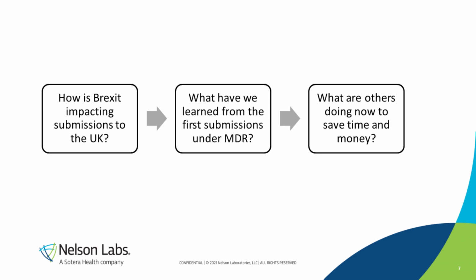And if you are submitting under the MDR and you have missed one of these steps, even if you've done the tests, even if the tests were done 20 years ago and it's been on the European market for 20 years, all that doesn't matter. You still have a gap to the current state-of-the-art standard. And we're seeing that being asked by notified bodies under the MDR. The other thing to keep in mind is that the notified bodies are also going to require you to show some kind of educational or experience proof of the individual making the assessment.